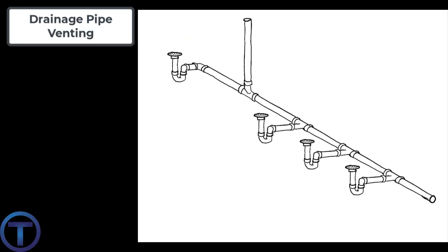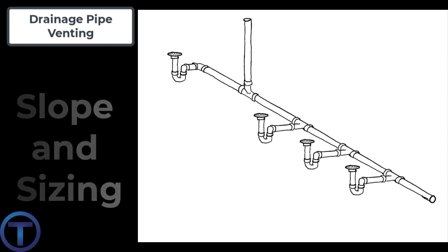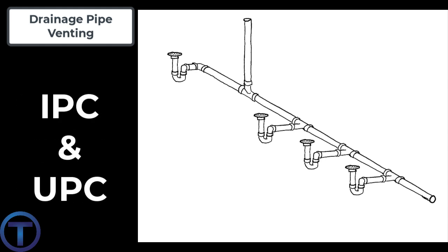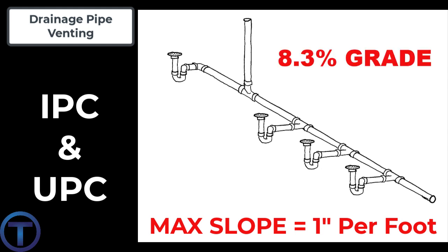Let's examine some code requirements for circuit vents regarding the slope and sizing of the pipe. Both the International and Uniform Plumbing Codes state that the slope for a circuit vent shall be no more than one inch per foot, or 8.3% grade. Let me point out — that is pretty steep slope. We're usually at quarter inch per foot or less. But in this case, a circuit vent can actually have a steeper slope.